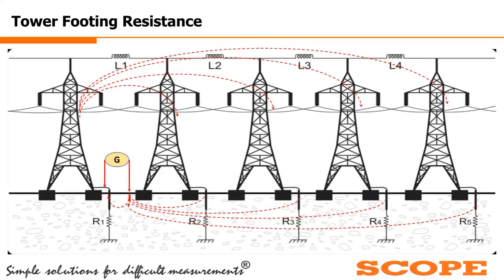So this is just a pictorial representation. This is the actual measurement of the tower footing of this particular tower, and these are the multiple paths which are created due to the connection of the guard wire between the adjacent towers. So these slides only represent the influence of adjacent tower resistance only.